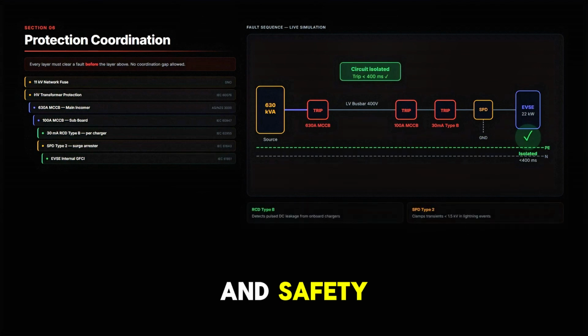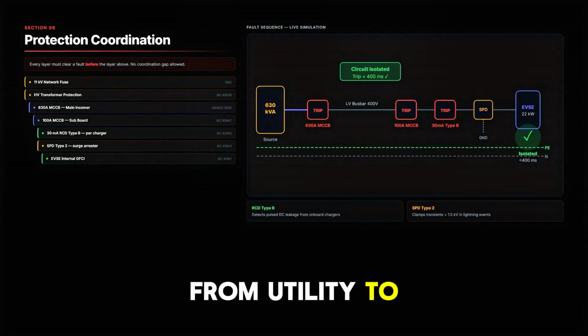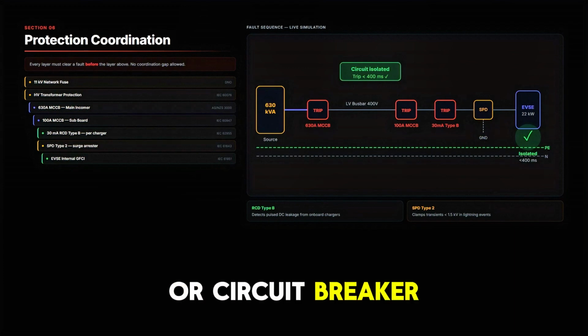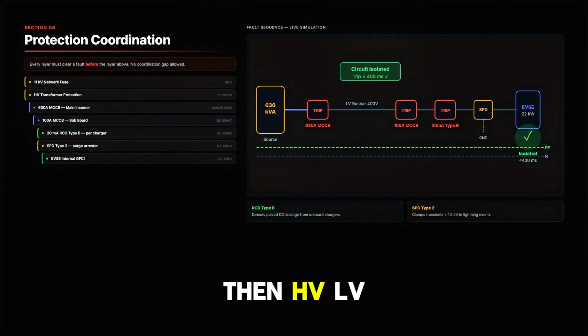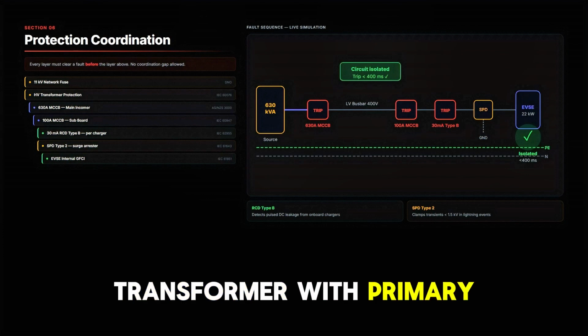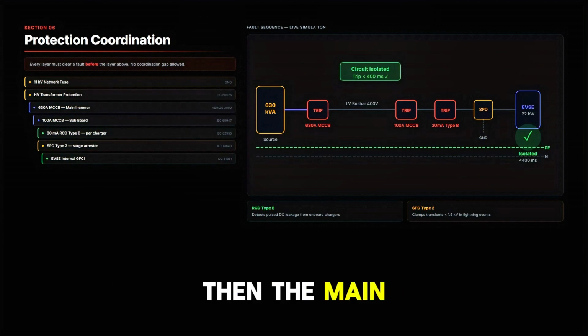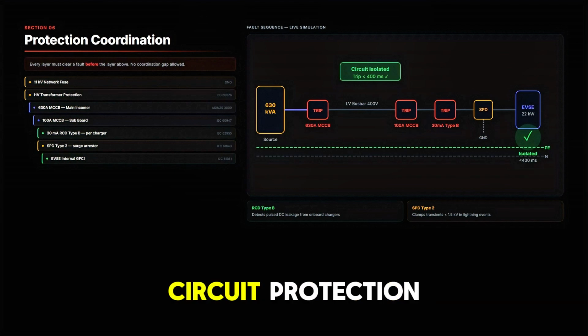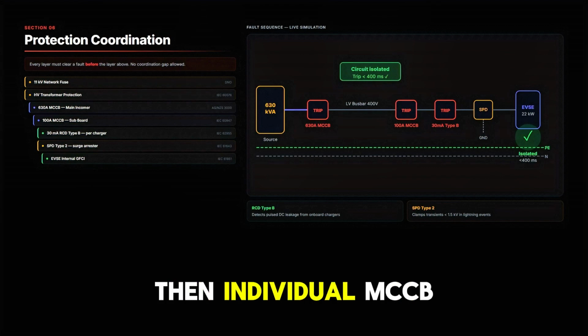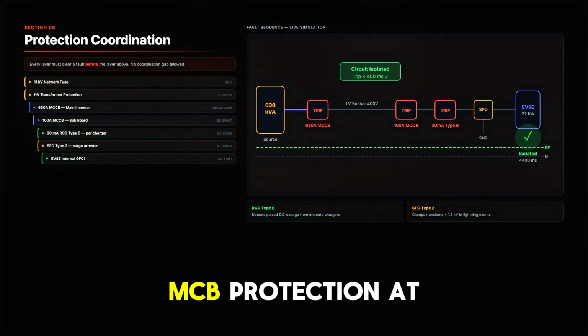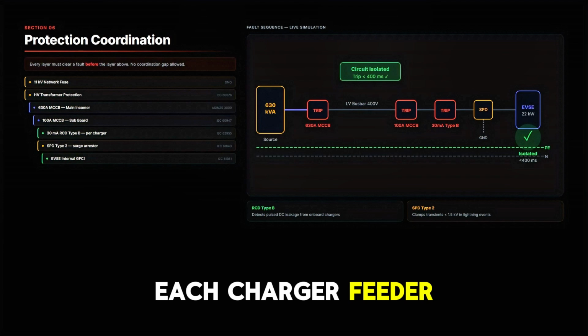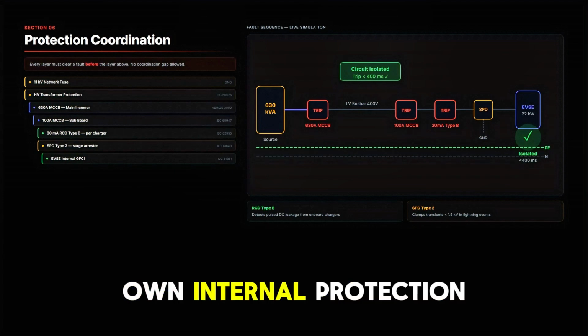Protection and safety. The hierarchy runs from utility to charger terminal. At the top, utility HV fuse or circuit breaker, protecting the network. Then HV-LV transformer with primary fuse protection. Then the main LV MCCB at the switchboard, 630 amps, with overload and short circuit protection. Then individual MCCB or MCB protection at each charger feeder. Then the charger's own internal protection.